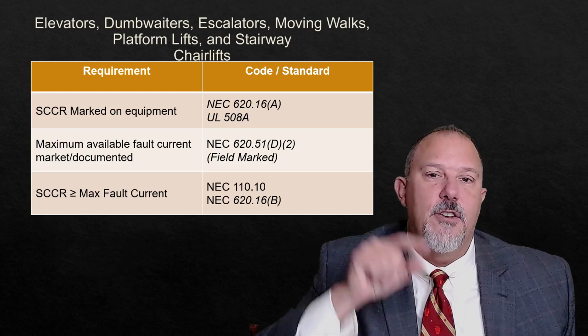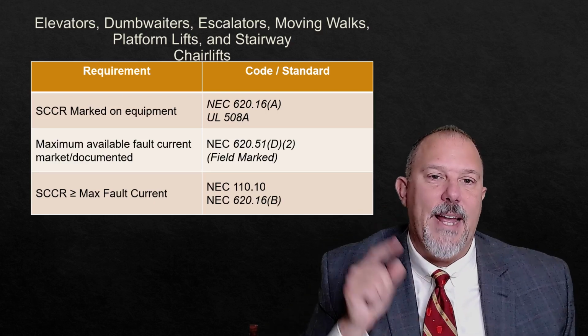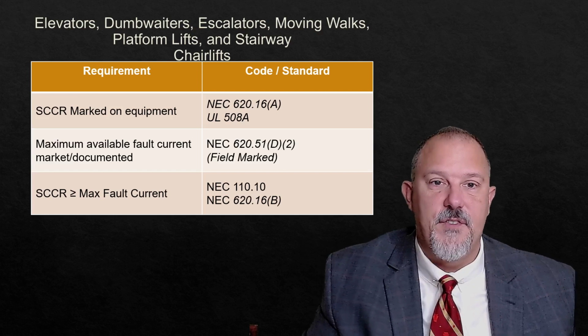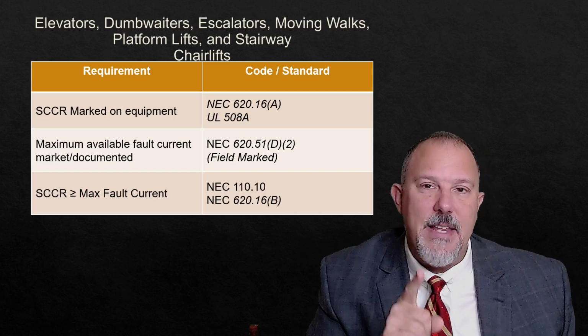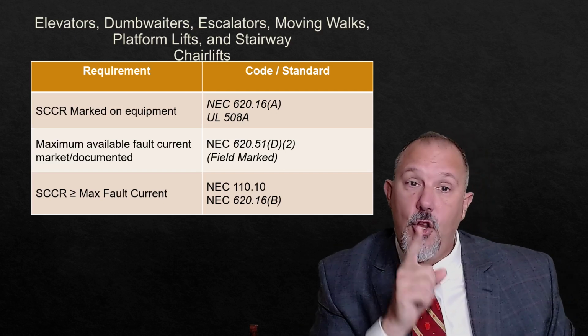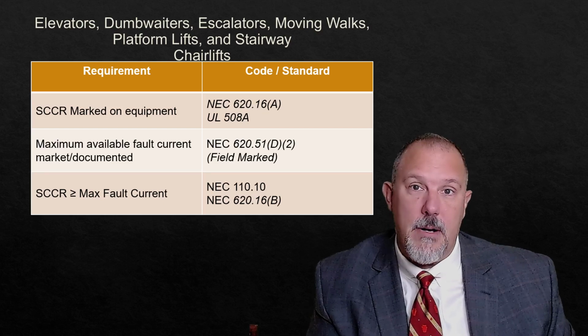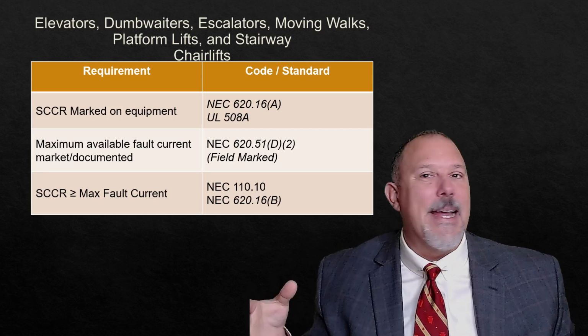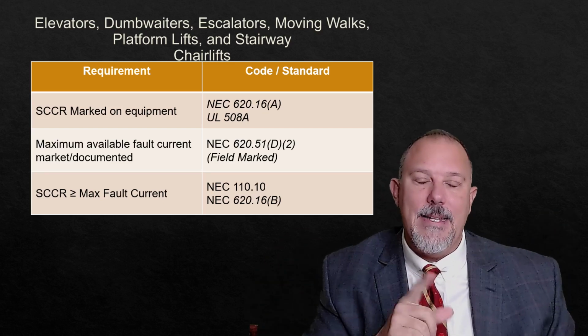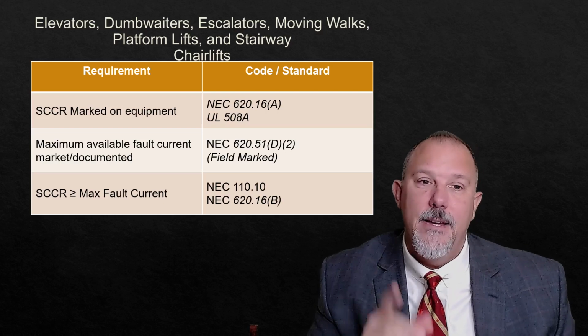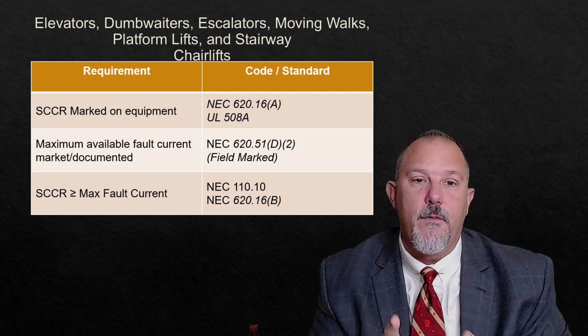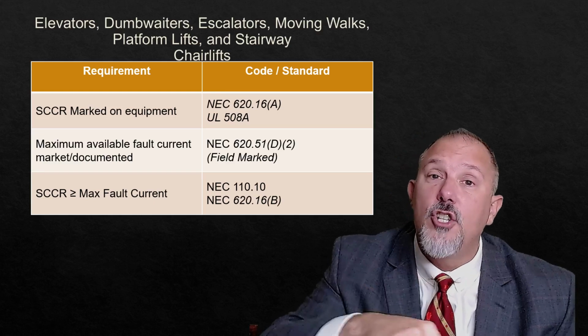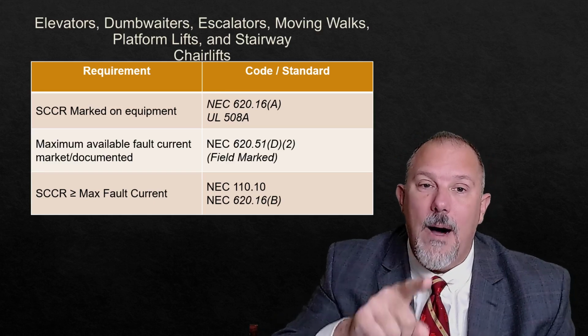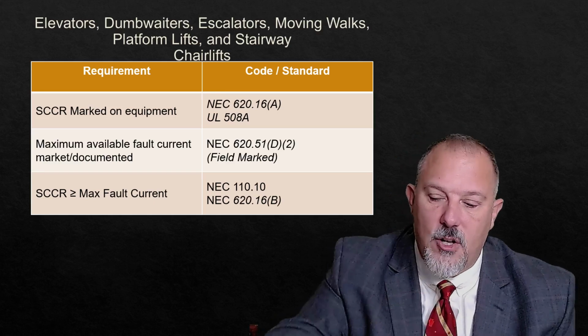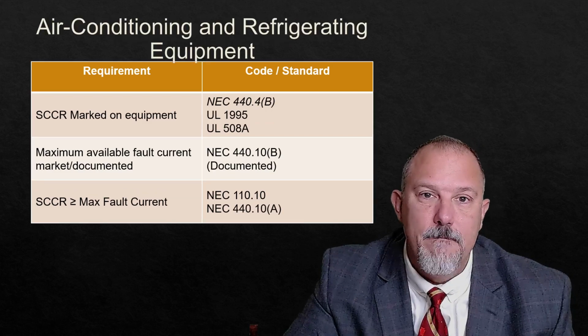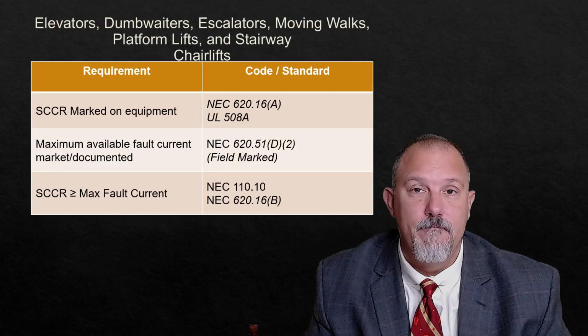Elevators, dumbwaiters, escalators, moving walks, platform lifts, and stairway chair lifts. You have to have the SCCR marked on the equipment. UL 508A, if you buy a listed product, it's in there. NEC 620.16A needs to be marked. Maximum available fault current needs to be marked on the equipment. Why does this need to be marked on the equipment, but the other one didn't? Two different code panels. That's all.